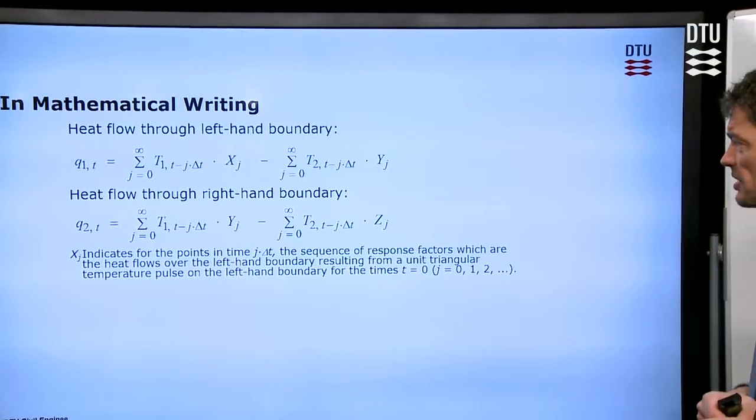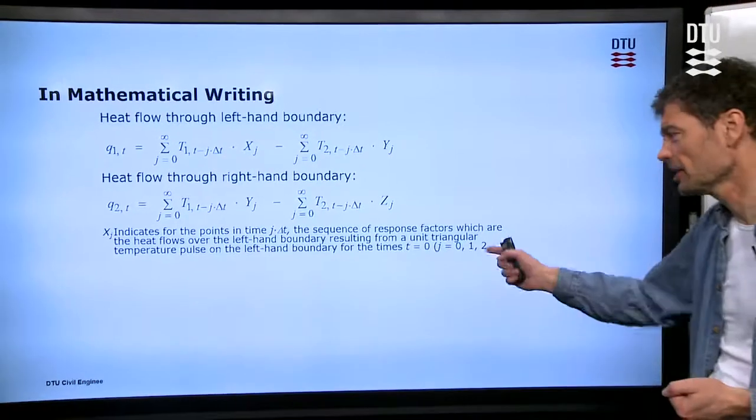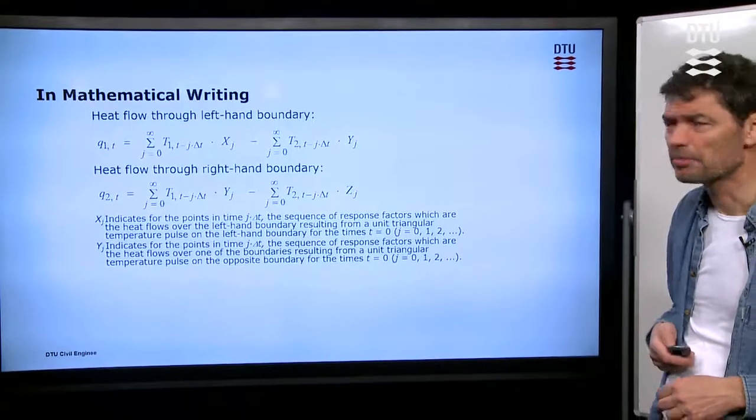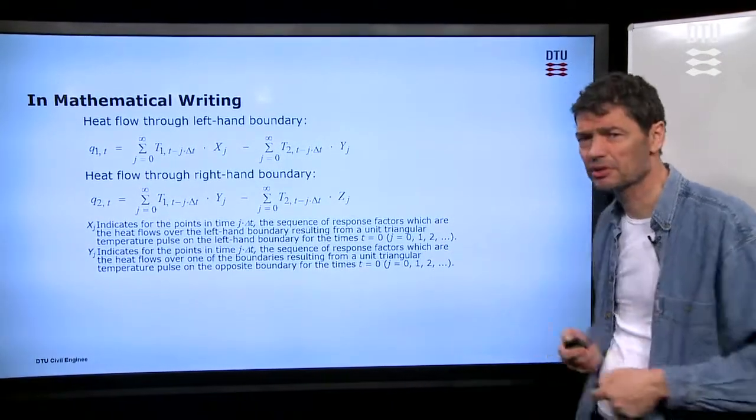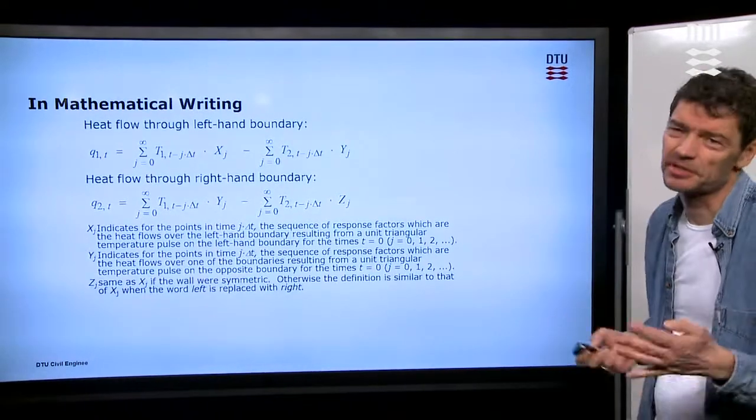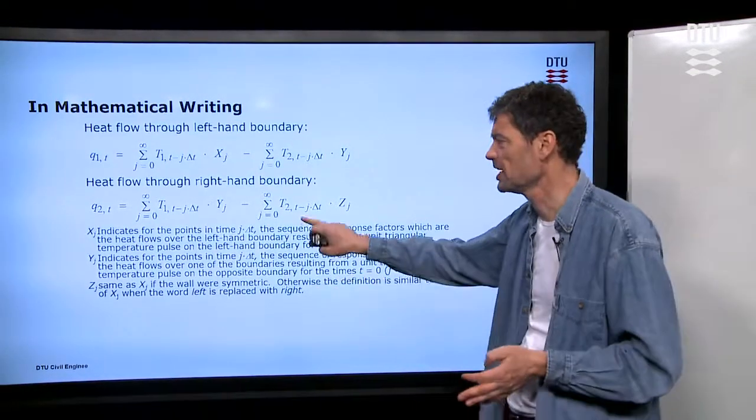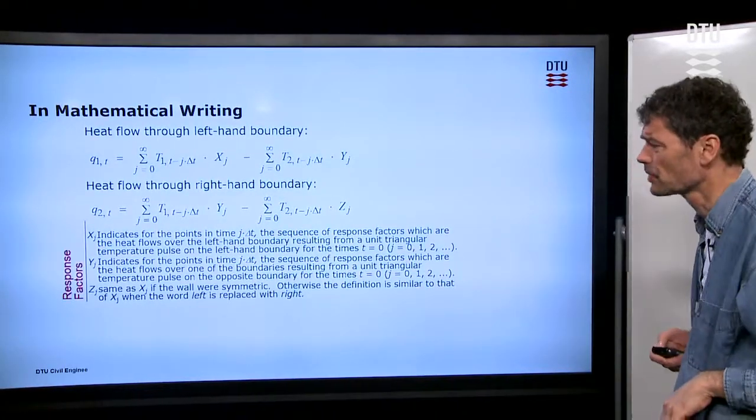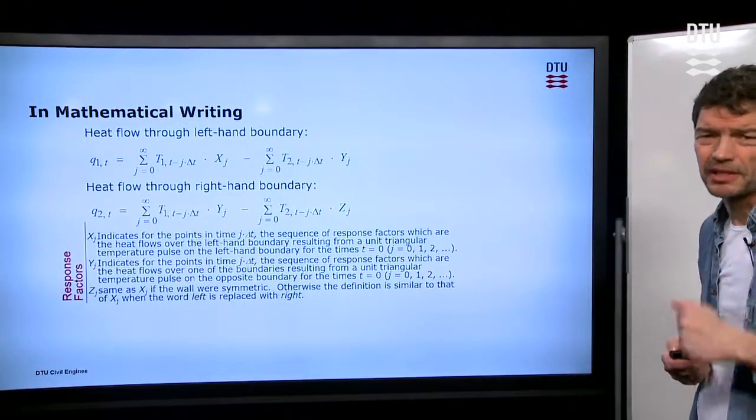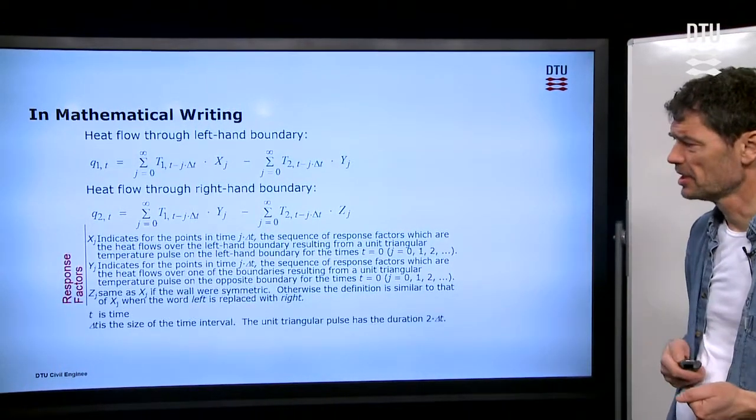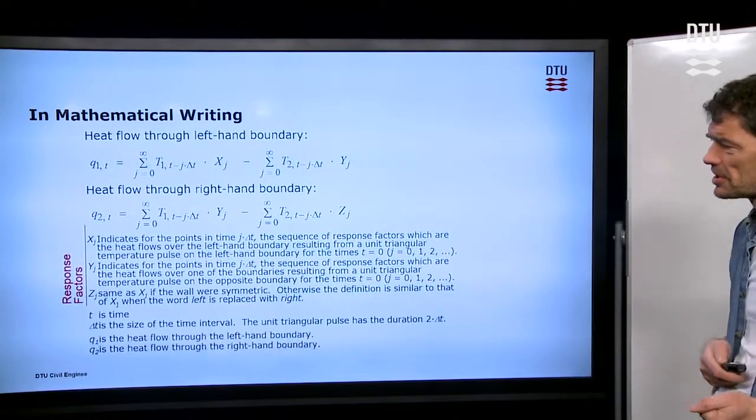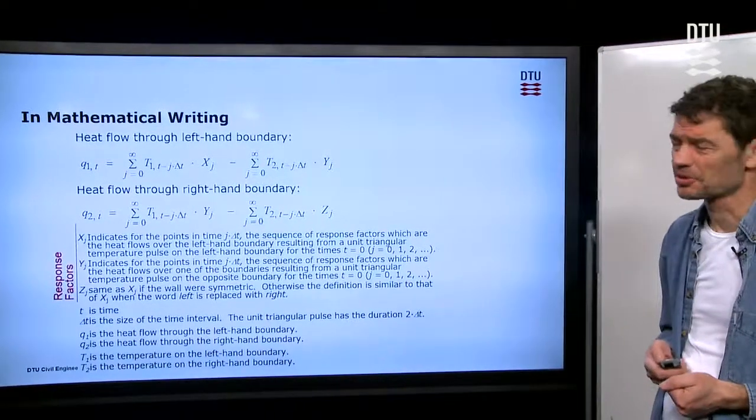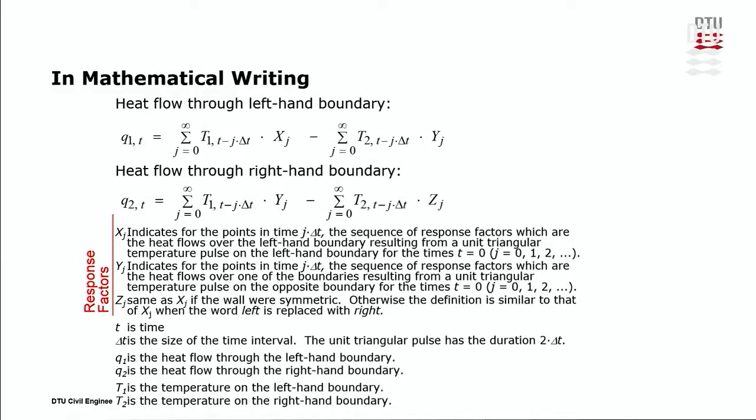So, we should have the X factors counted back in time and number of hours, and remember those. Y factors are needed as well for the cross-going influences. And then we have, of course, the Z factors, which are quite similar to the X factors, on either the left-hand side or the right-hand side of the wall. Those are our response factors, which are the factors that have given name to this method. T, of course, is time. Q are the heat fluxes.